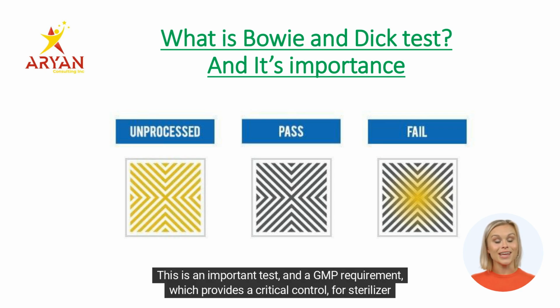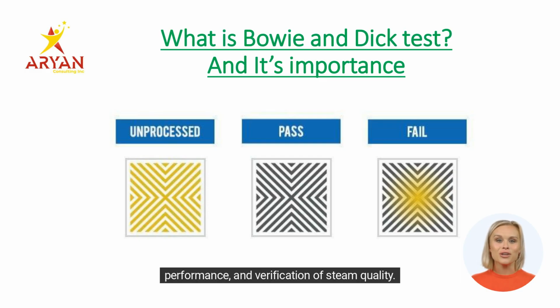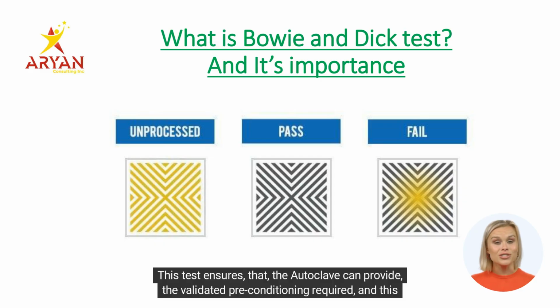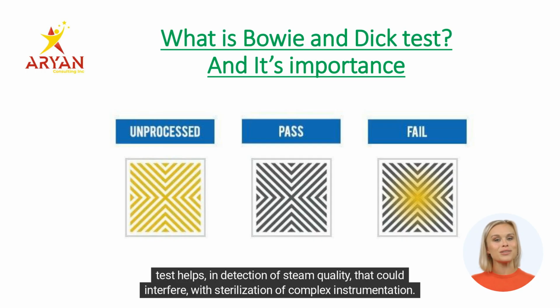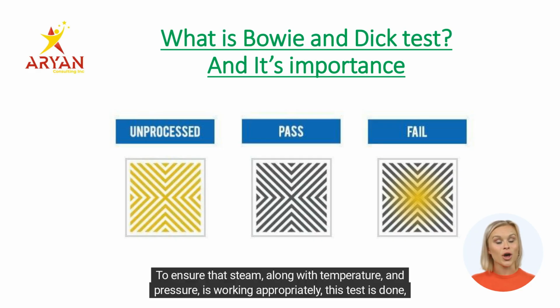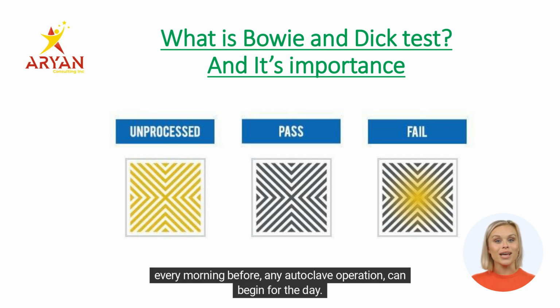This is an important test and a GMP requirement which provides a critical control for sterilizer performance and verification of steam quality. This test ensures that the autoclave can provide the validated preconditioning required, and this test helps in detection of steam quality issues that could interfere with sterilization of complex instrumentation. To ensure that steam, along with temperature and pressure, is working appropriately, this test is done every morning before any autoclave operation can begin for the day.